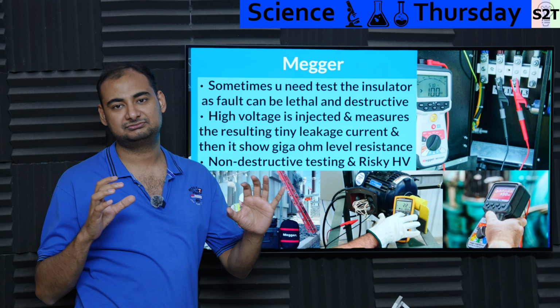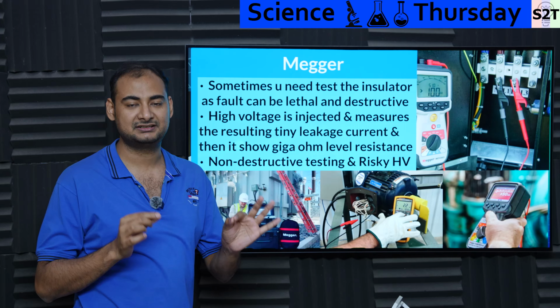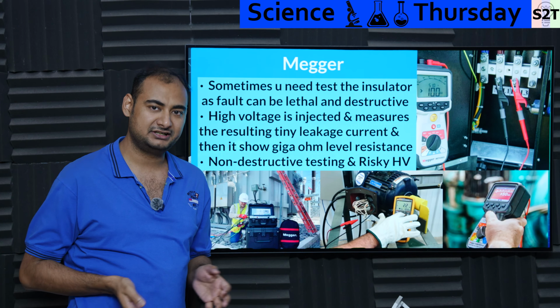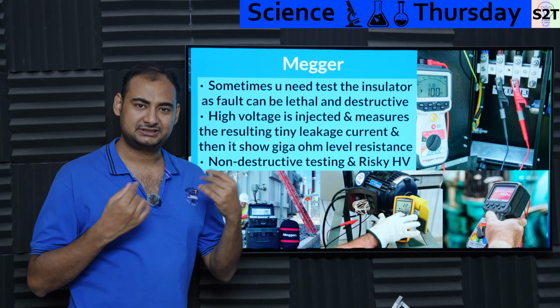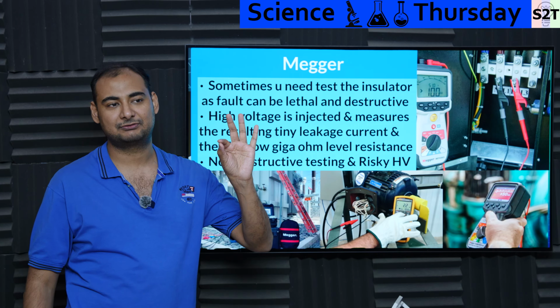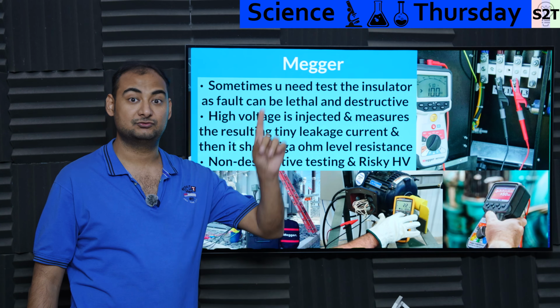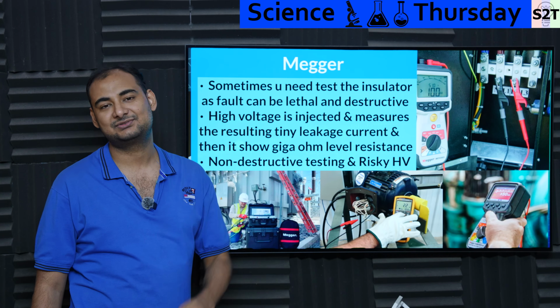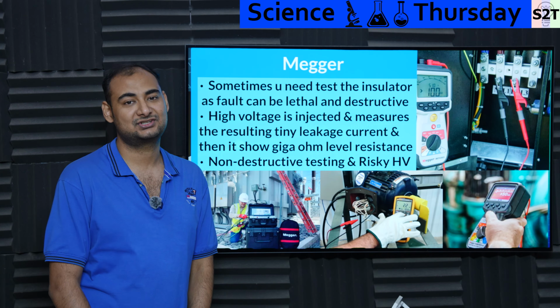You have the same wire thickness, insulation thickness, for household wiring, because they're generally tested for 1000 volts. So thickness stays the same even though you can go from, say, 18 gauge to 4 gauge. Insulation thickness won't change that much. Why? Because the voltage didn't change.